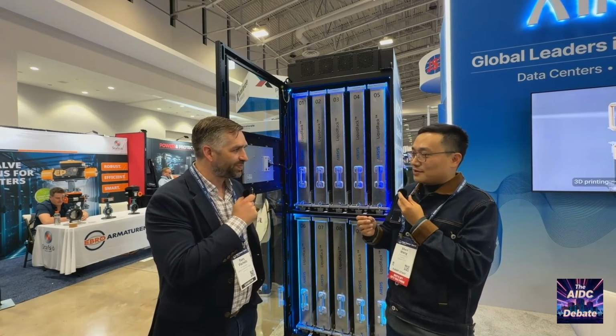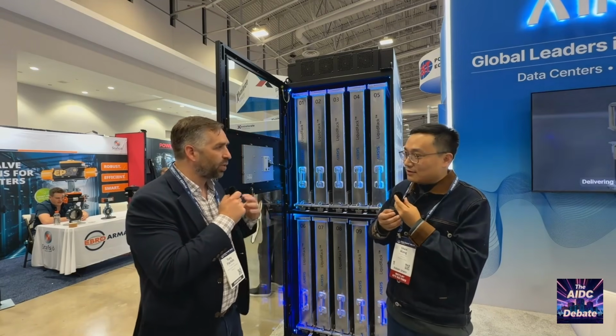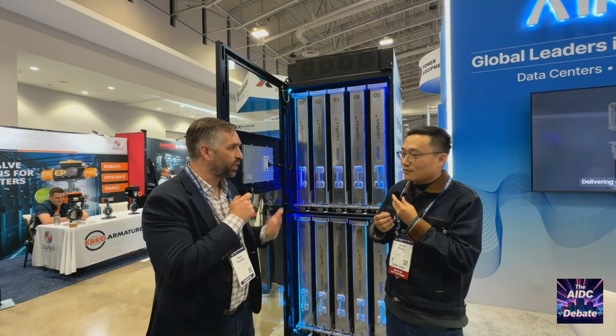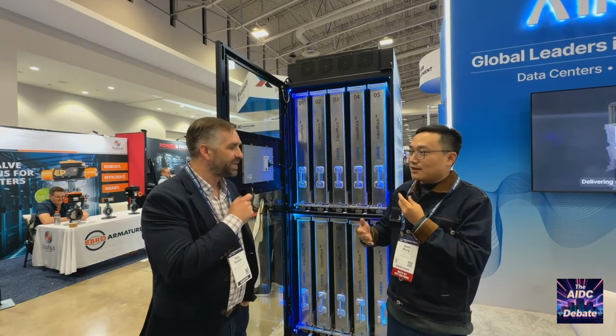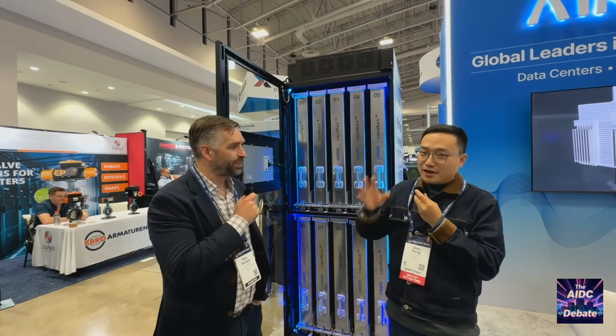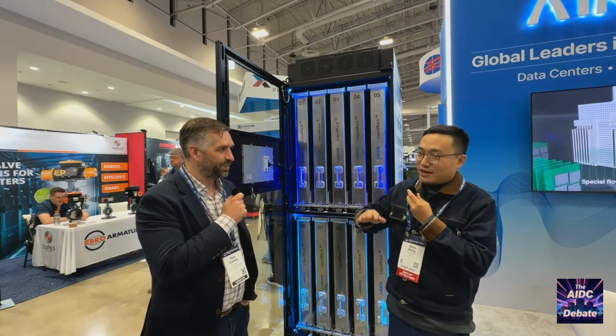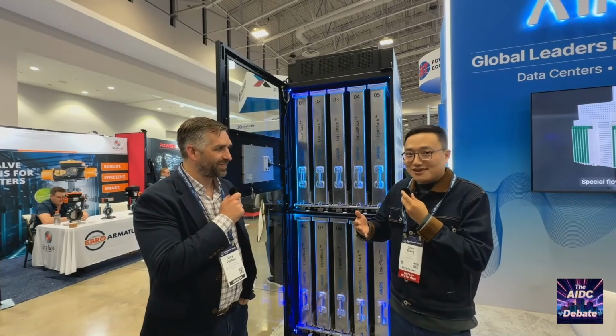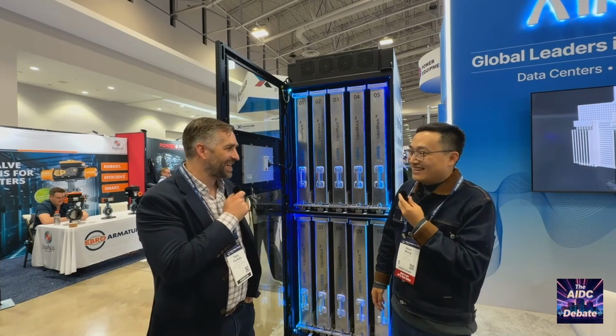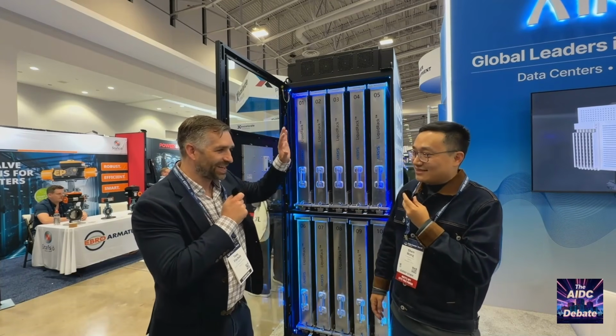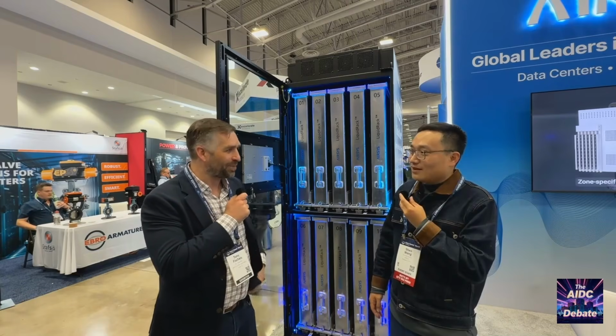So what is the liquid in the spray? It's like an oil substance, think of it as vegetable oil or mineral oil - a dielectric fluid. So it's sprayed directly onto the hottest spots and flows down through the other not-so-hot spots. You could think of it like you're spraying, but then there's kind of a waterfall coming down the rest of the server.